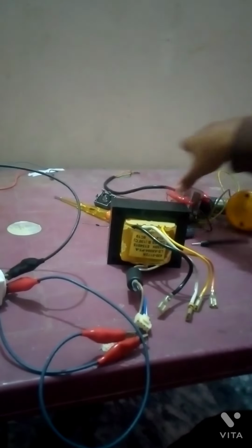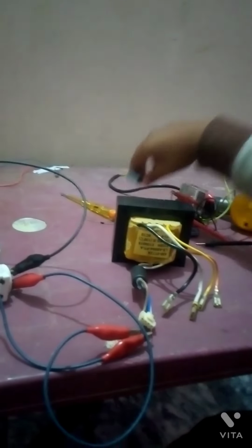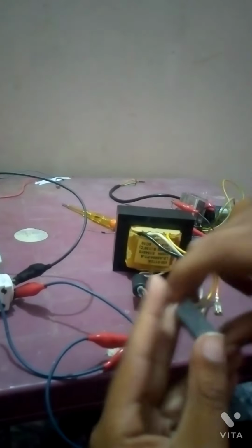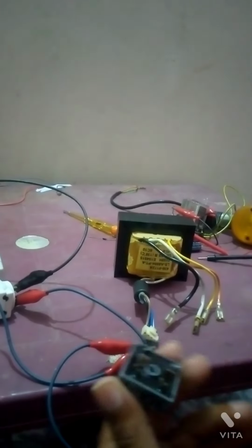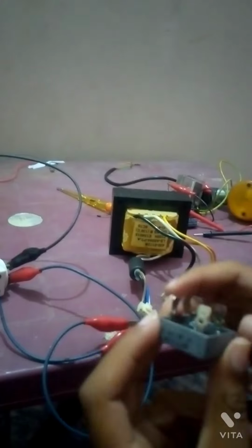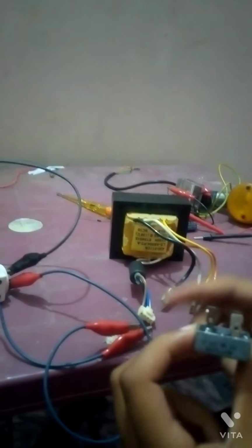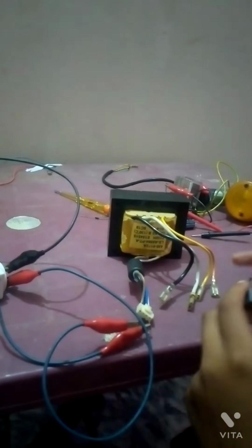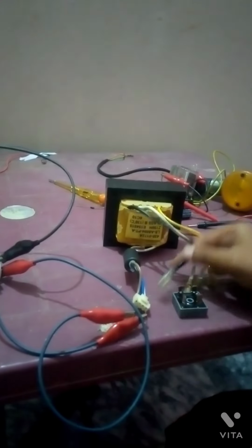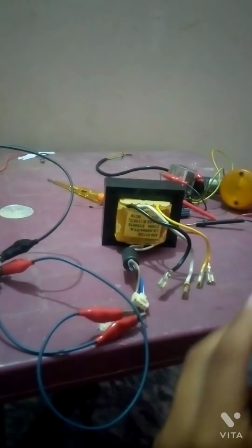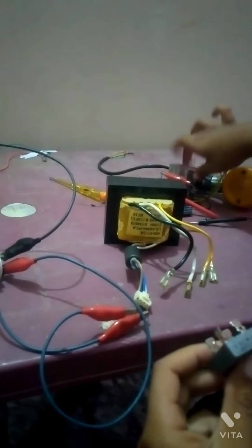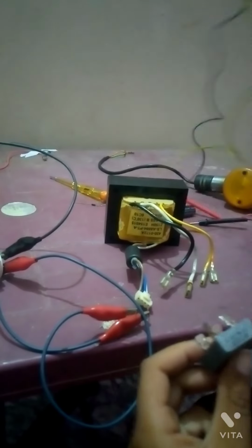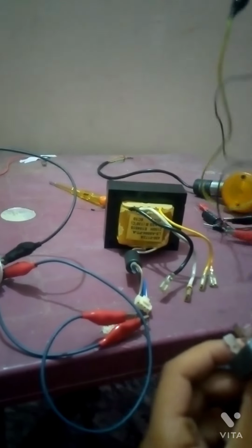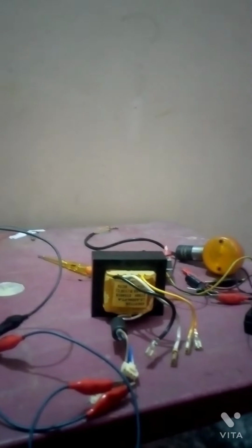This time, you might say this is AC voltage. When you convert it to DC voltage, it's boosted up a bit, because AC reading is an average voltage. When you use a rectifier for DC, it comes out as a peak voltage, and peak voltage is always higher than average voltage. Now let's use a rectifier to convert it and measure the DC voltage with this voltmeter, to check if there's any difference.